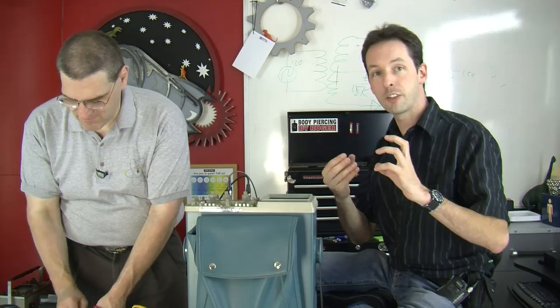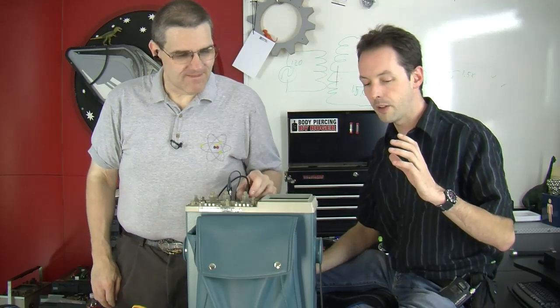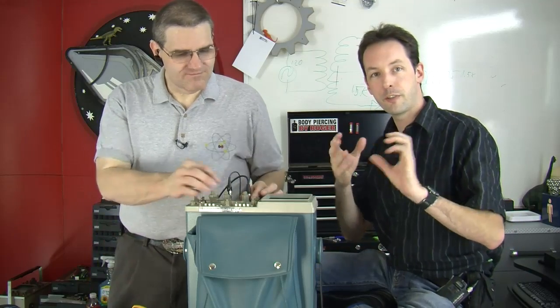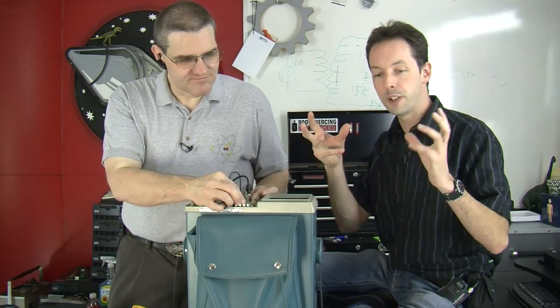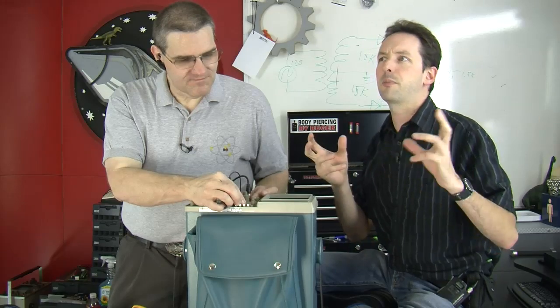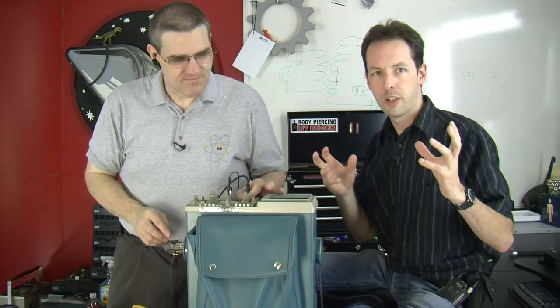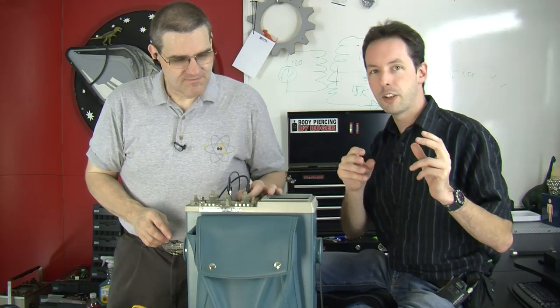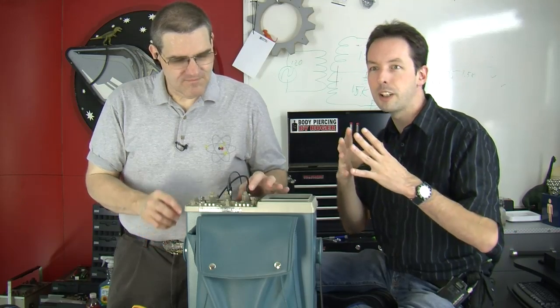In an X-ray transformer, which you've seen us play with in a lot of videos in the past, there's actually more than one transformer. You have to have a very high current but very low voltage power supply that feeds the filament in the X-ray tube. Now, the wires that are feeding this transformer, that feed this tube, the tube is insulated at like 150,000 volts. So they only need 3 volts, like 3 or 6 volts.